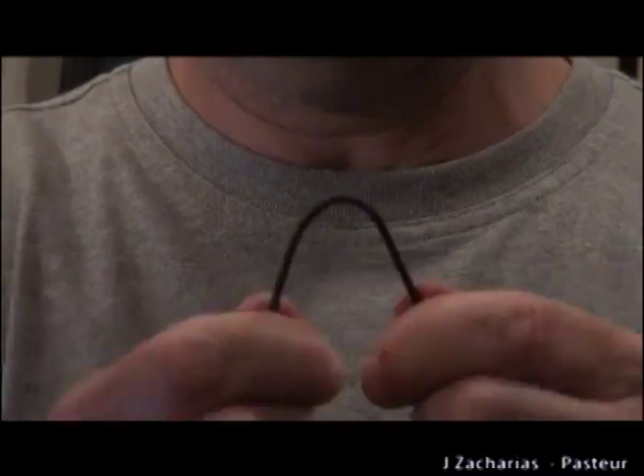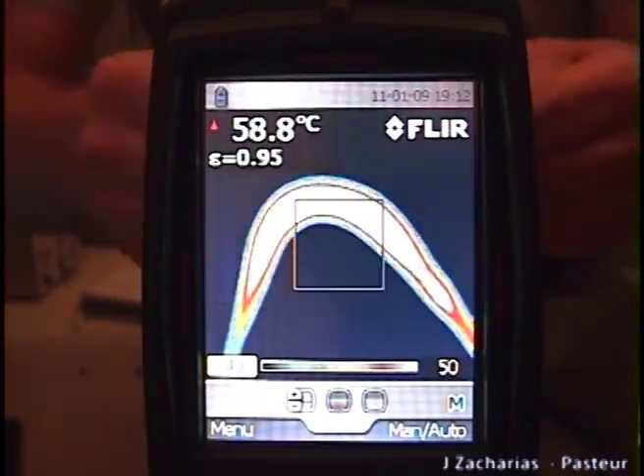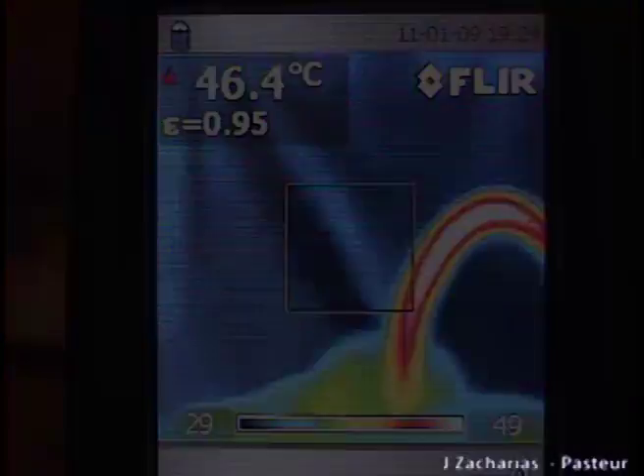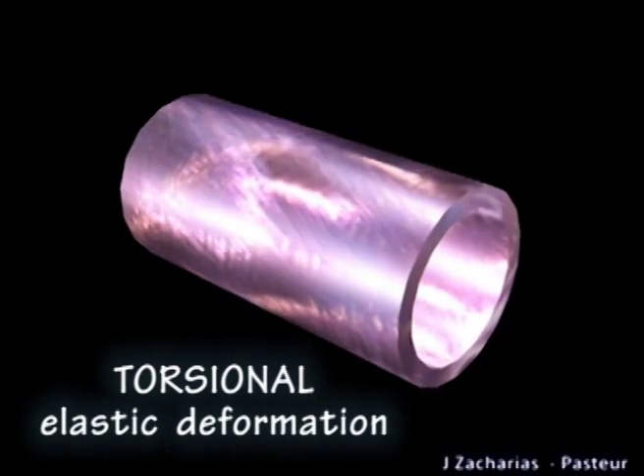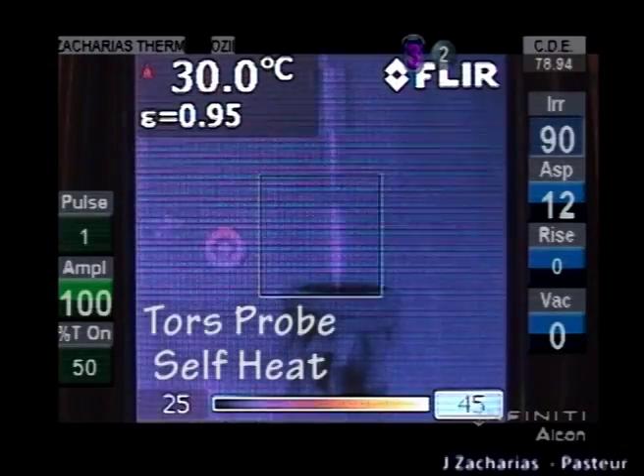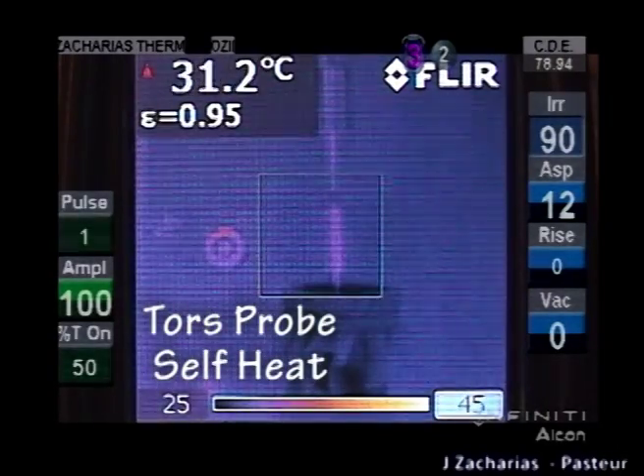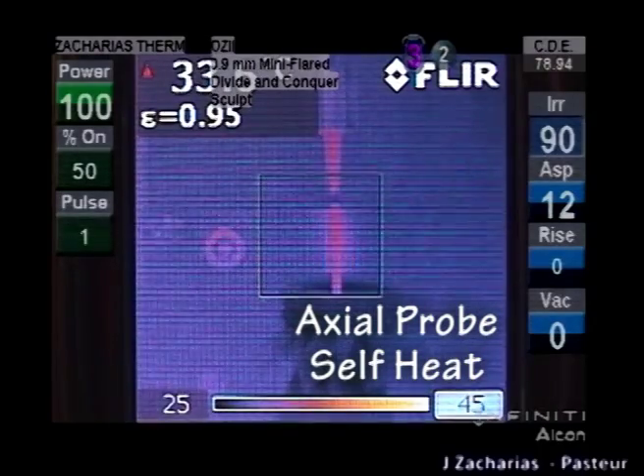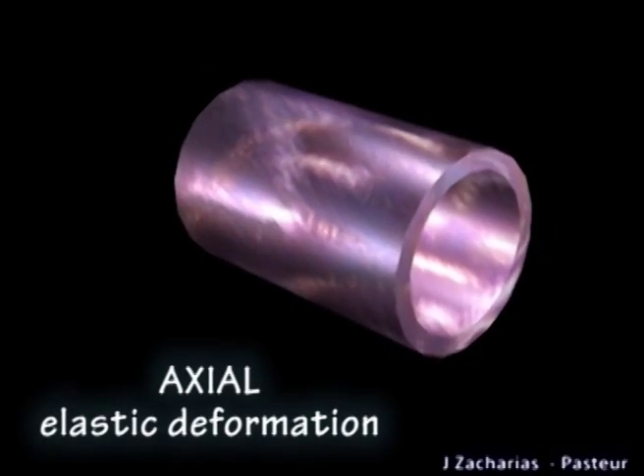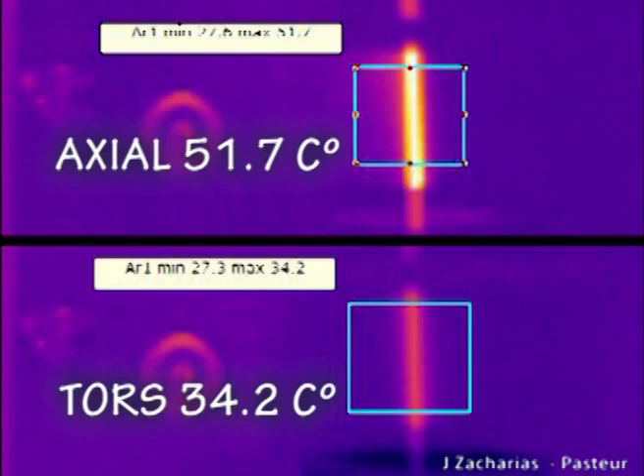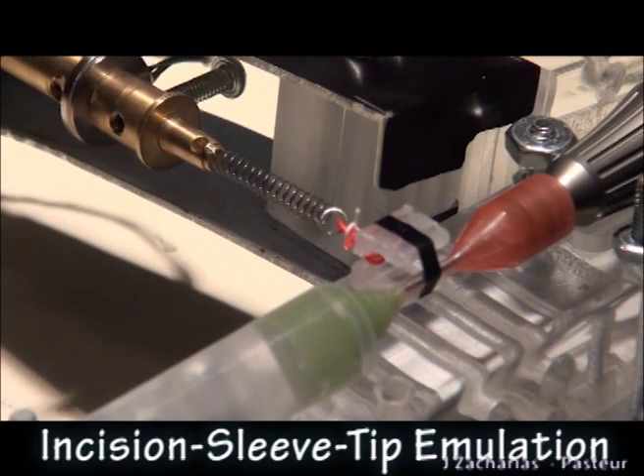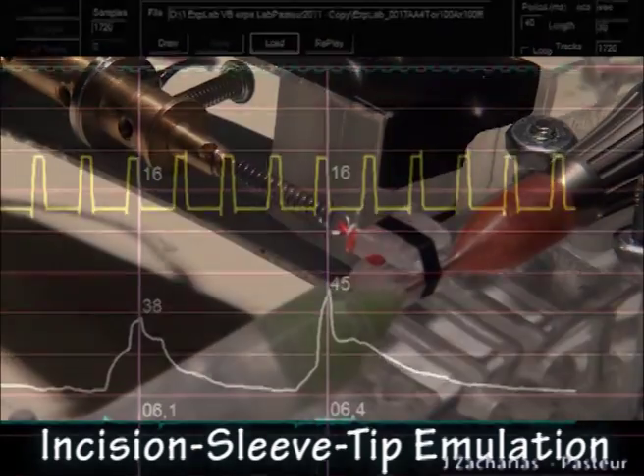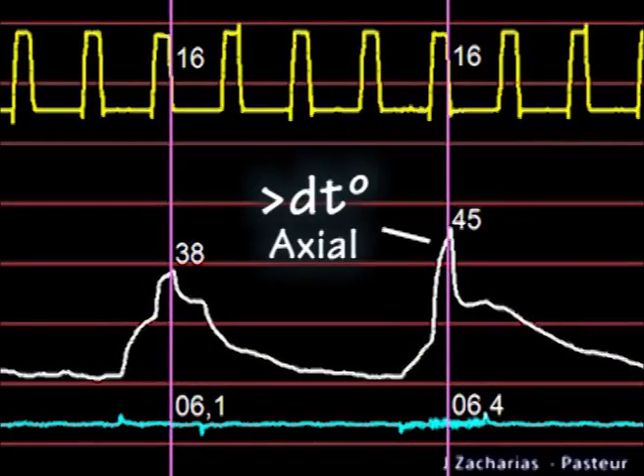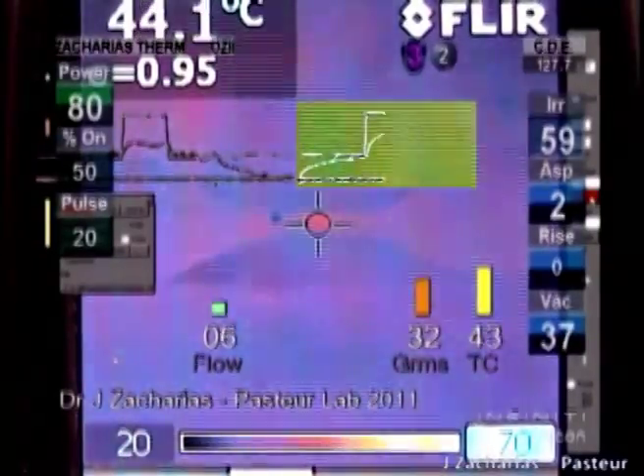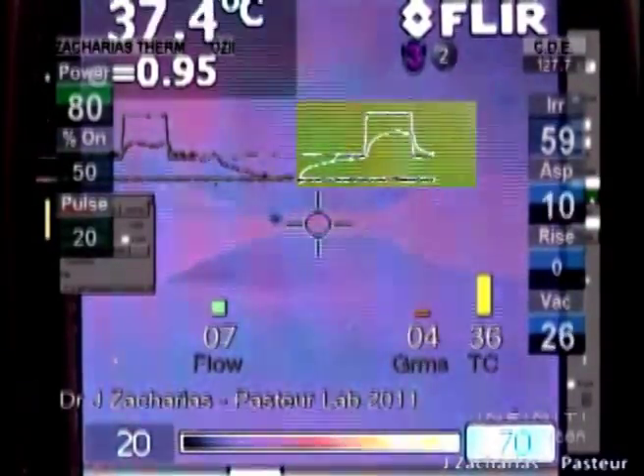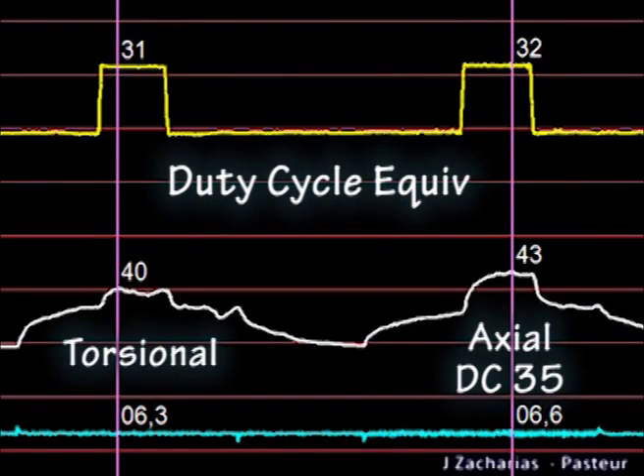A rigid wire bent repeatedly is subjected to plastic deformations, heating up by internal metal stress. The theory of internal metal stress as a dominant source of heat only with torsional is challenged by these bare probe tests showing that self-heating is more relevant with axial. Differences in elastic deformation could explain greater self-heating with axial. Probes with a sleeve simulating incision conditions also demonstrated that axial produces more heat, especially under load. Heat produced by continuous torsional could be matched to a duty cycle between 30 and 50% using axial.